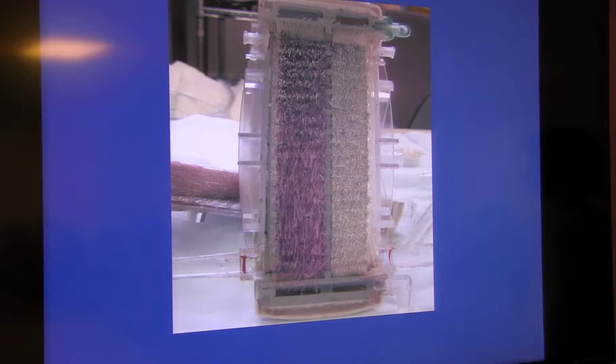And we set it at 35. How much heat do they usually lose from the membrane to the patient, from your experience? If it's set at 36 here, what is the patient's actual temperature usually? 36 and a half, 37. So if we're running normothermia, if that's set somewhere between 36 and 37 or as high as 38, then your patient's temperature is going to be normothermic. That's why you can't rely on it to tell you whether your patient has a fever or not. For hypothermia, this is amazing to have in your world.